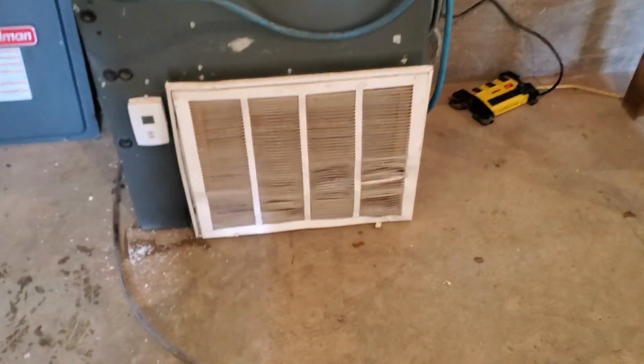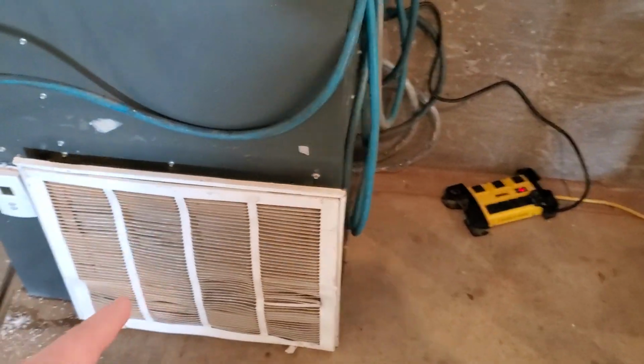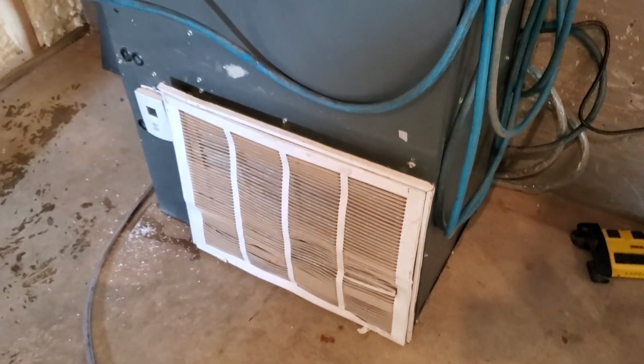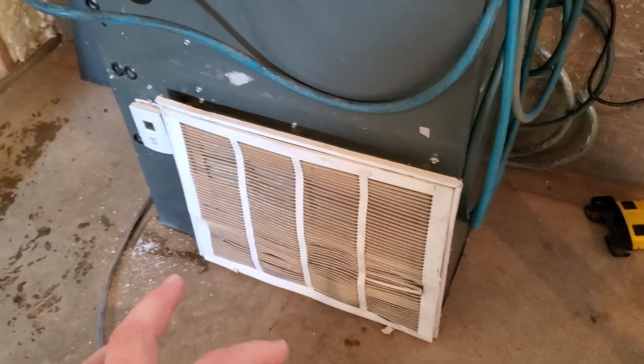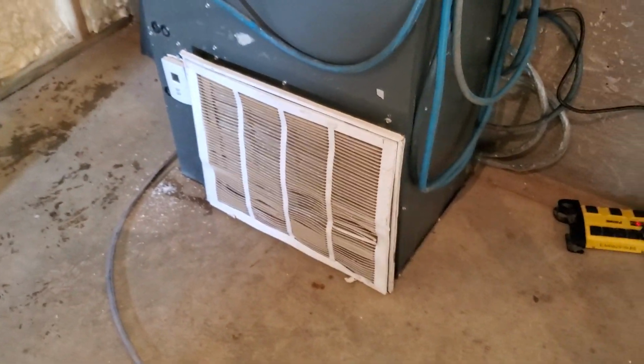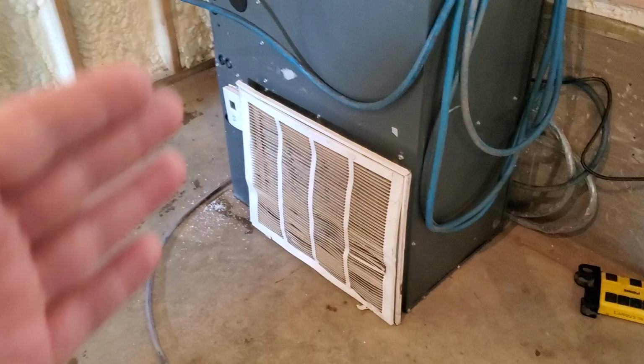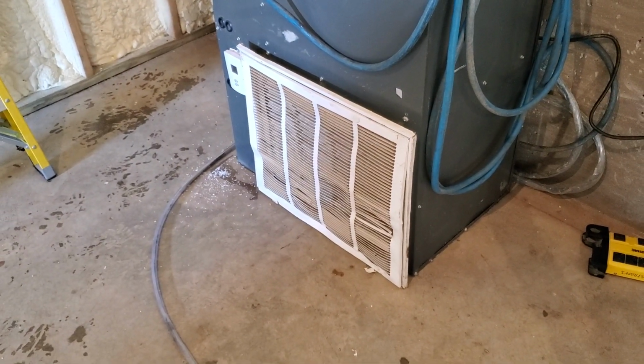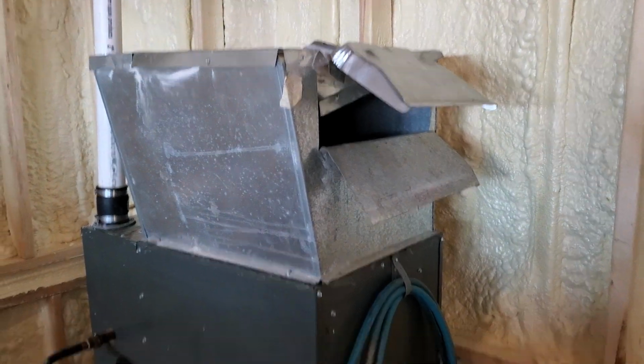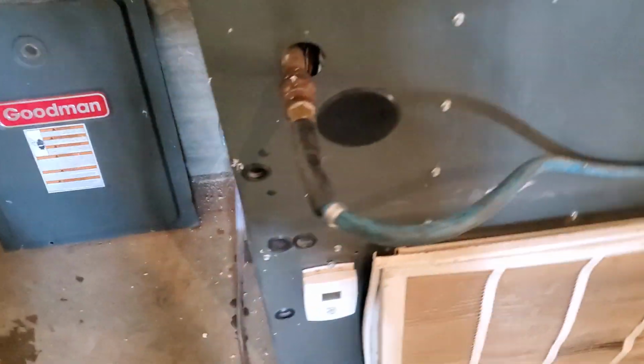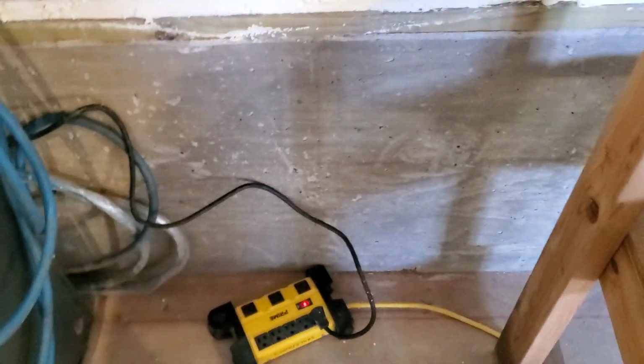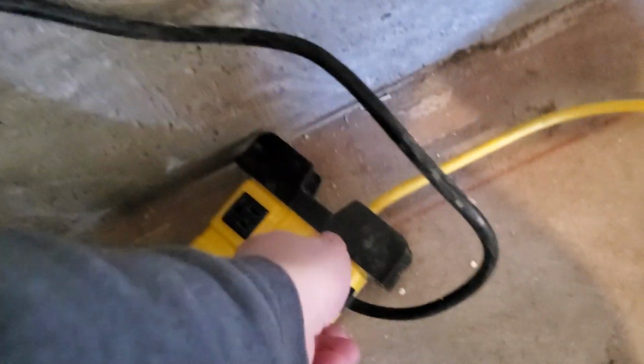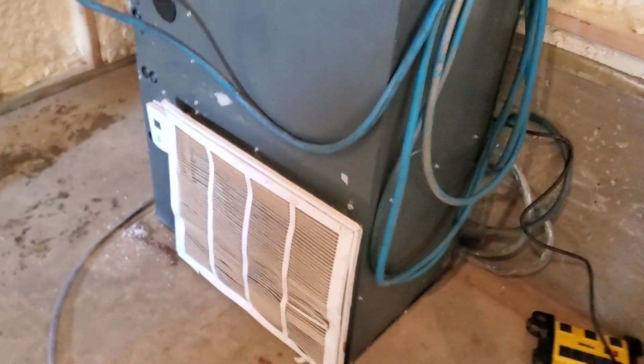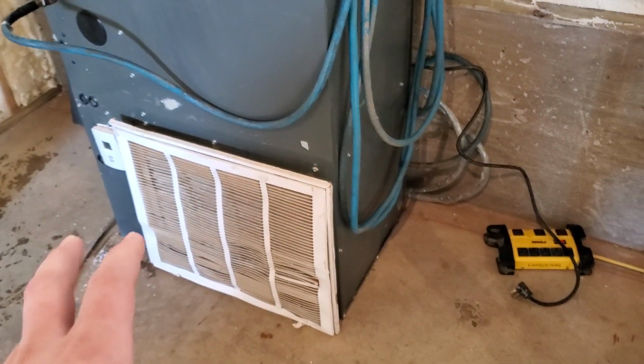And that brings me over to this side of the furnace here. You can see we have a filter rack assembly installed on the side of this furnace. Making sure that you have a good filter, especially in a bad environment like what a temporary furnace is going to be set up in, is really important. There comes the main blower. I'll shut this thing off here for the moment. I'm just going to unplug it. So yeah, having a good filter installed is important to keep drywall dust and stuff out of it as much as possible.